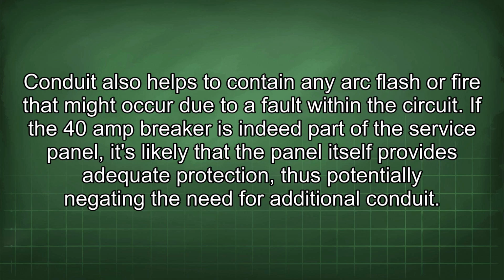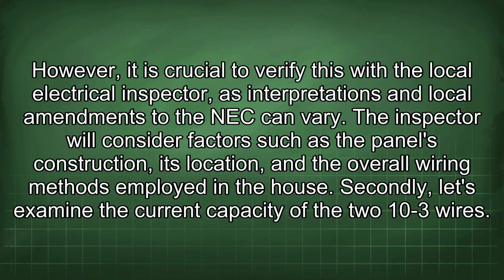If the 40 amp breaker is indeed part of the service panel, it's likely that the panel itself provides adequate protection, thus potentially negating the need for additional conduit. However, it is crucial to verify this with a local electrical inspector, as interpretations and local amendments to the NEC can vary. The inspector will consider factors such as the panel's construction, its location, and the overall wiring methods employed in the house. Secondly, let's examine the current capacity of the 10-3 wires.